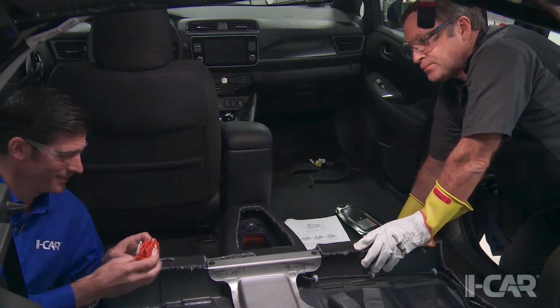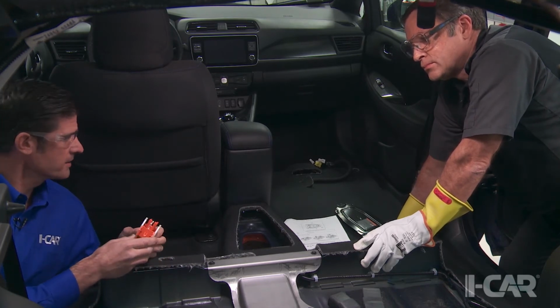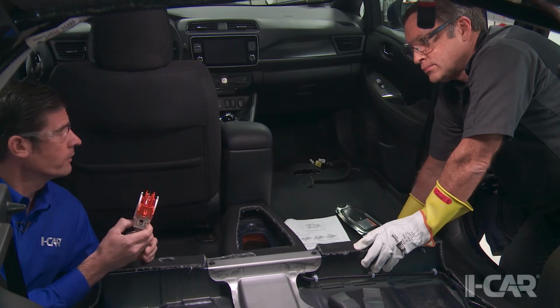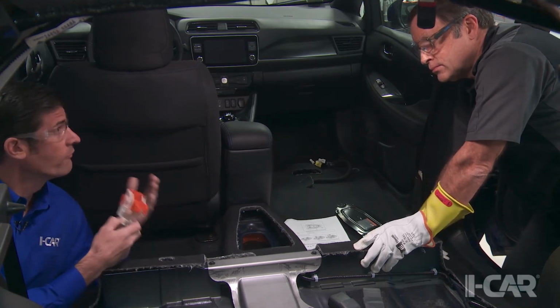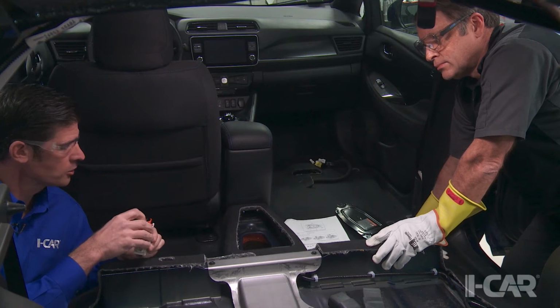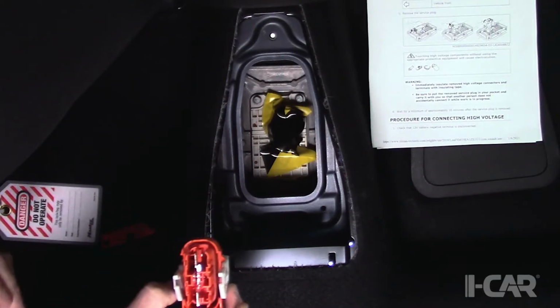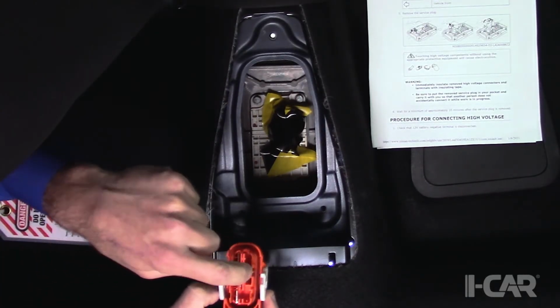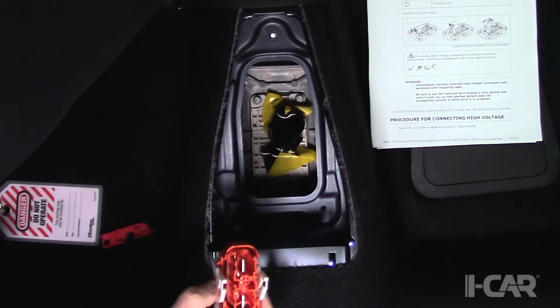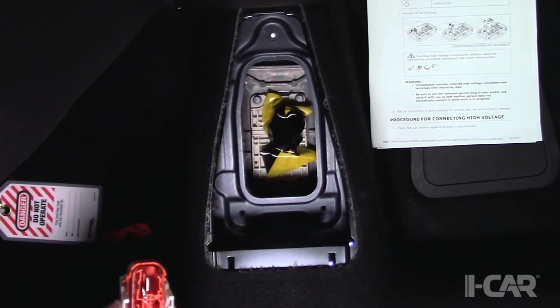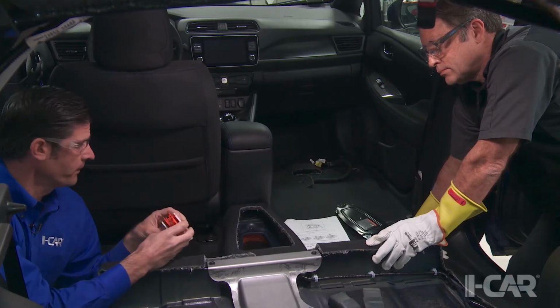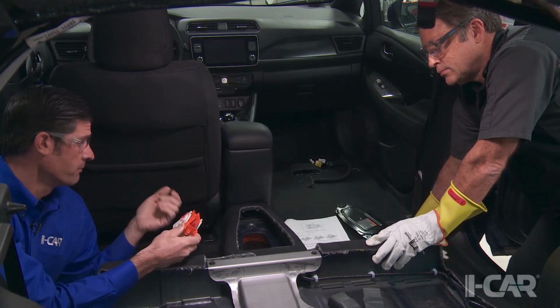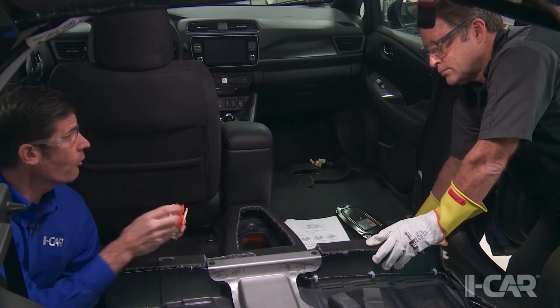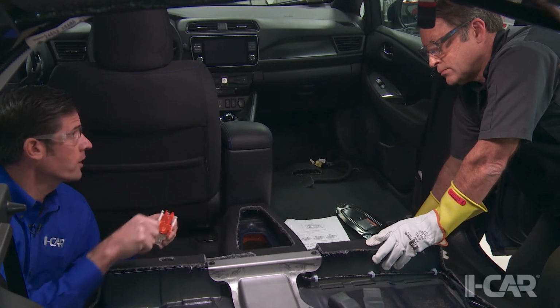We call it interlock. The interlock runs through every component, every plug in the whole high voltage system. I'll hold it under the camera so you can see here in the middle those 2 little pins. That means once you remove that plug, or that battery disconnect, we interrupt the circuit of the interlock.